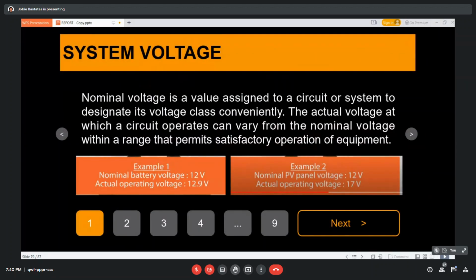System voltage is also known as nominal voltage. It is a value assigned to a circuit or system to designate its voltage class conveniently. The actual voltage at which a circuit operates can vary from the nominal voltage within a range that permits satisfactory operation of equipment. So nominal voltage conveniently designates the rating of one piece of equipment to help match up with another piece of equipment. Nominal ratings help match batteries, solar panels, charge controllers, and loads.